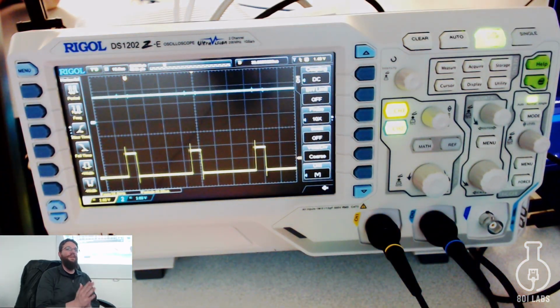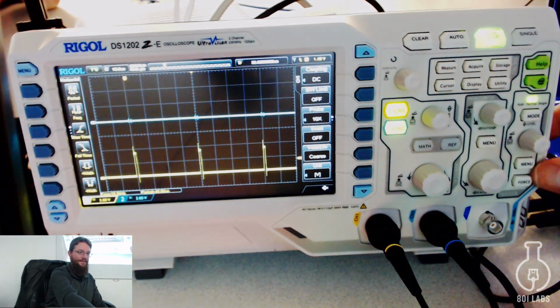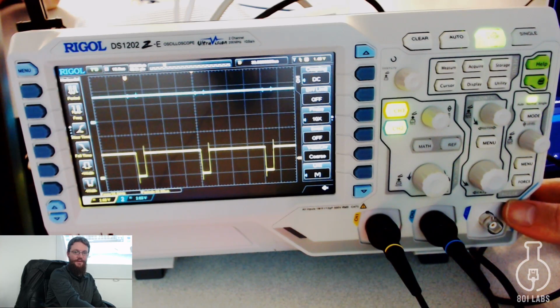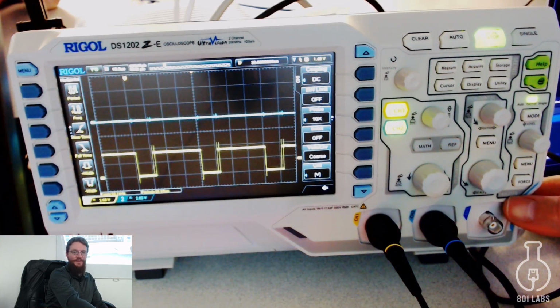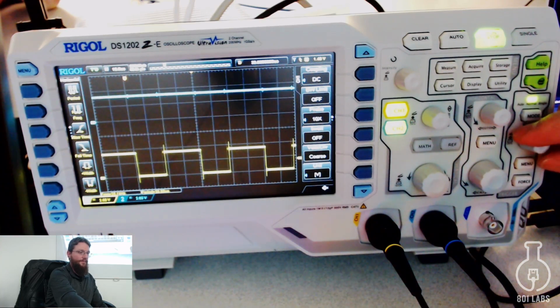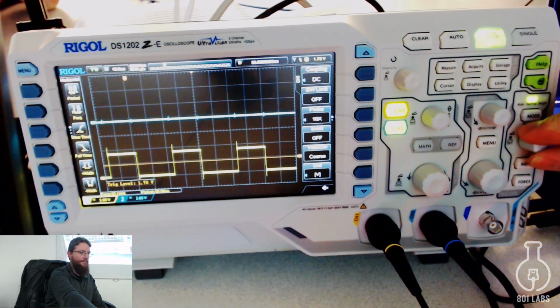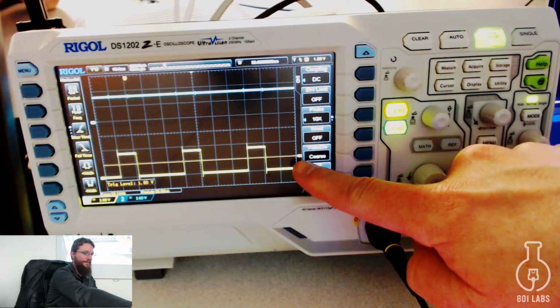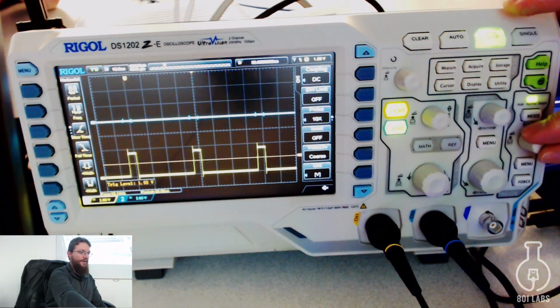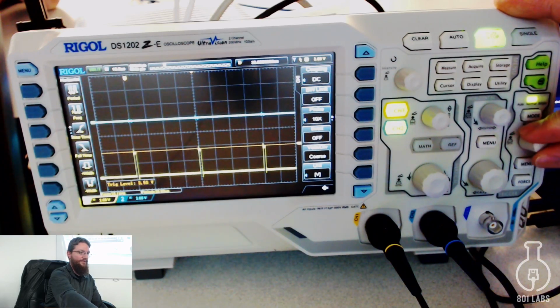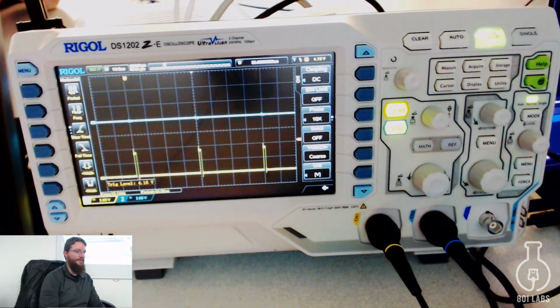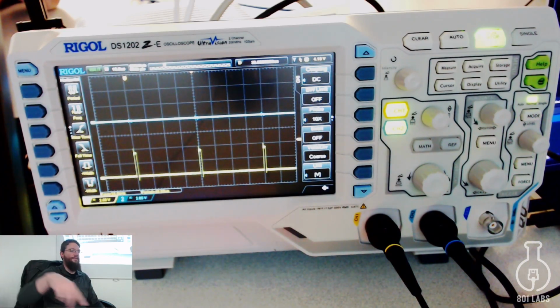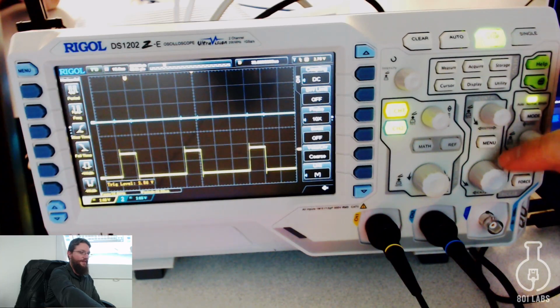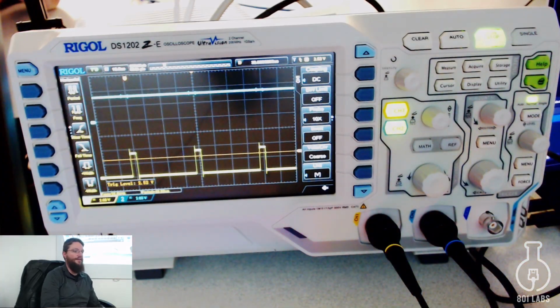So this whole time I've been talking about triggers a lot, and this third menu here is called the trigger menu. It says trigger there, it's kind of hard to read on the camera. But you'll see as I turn this knob, that orange line appears, and there's the little letter T on the side here. If I slide this letter T up above where the voltage signal is, you can see it stopped updating completely because it's no longer triggering at all. If the voltage does not go past the trigger line, it doesn't trigger. Now if I slide it back down, you can see it immediately started triggering again.